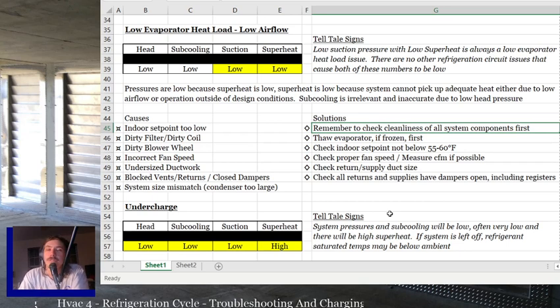Make sure the indoor set point's not super low. Check proper fan speed. Check the unit to make sure the fan speed is set to manufacturer's recommendations based on the static pressure that you have in the system. If you're unsure, just set it on high. That's what most guys do anyway, set it on high. That's not always right. It's right more often than not these days, but set the evaporator on high if it's on a different speed, and see if that makes any difference on the airflow that you're getting.